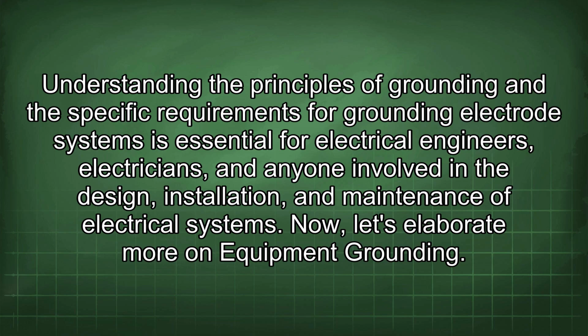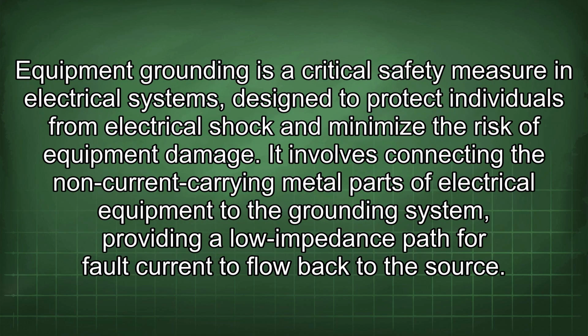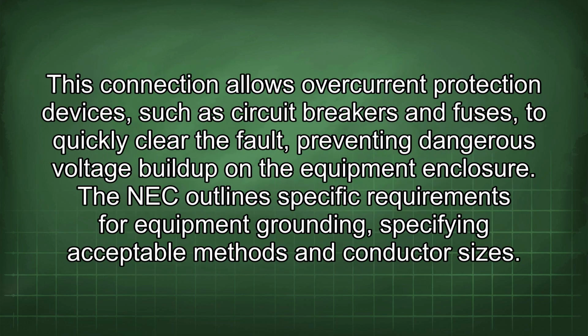Now, let's elaborate more on equipment grounding. Equipment grounding is a critical safety measure in electrical systems, designed to protect individuals from electrical shock and minimize the risk of equipment damage. It involves connecting the non-current carrying metal parts of electrical equipment to the grounding system, providing a lower impedance path for fault current to flow back to the source. This connection allows overcurrent protection devices, such as circuit breakers and fuses, to quickly clear the fault, preventing dangerous voltage buildup on the equipment enclosure.